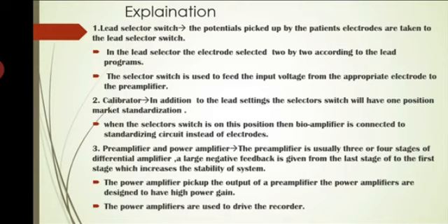Third, preamplifier and bioamplifier. The power amplifier is nothing but the bioamplifier. The preamplifier is usually 3 or 4 stages of differential amplifiers. A large negative feedback is given from the last stage to the first stage of the amplifier, which increases the stability of the system.